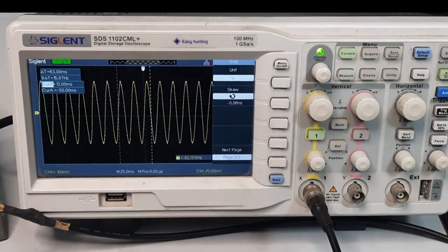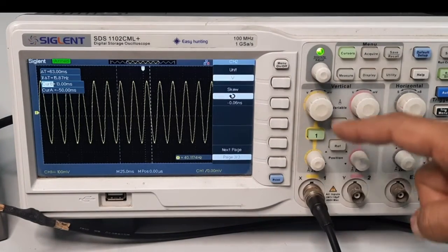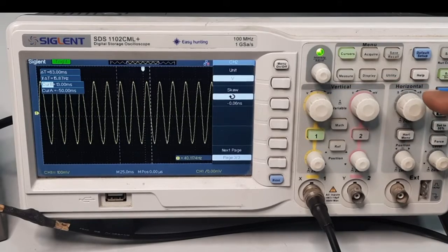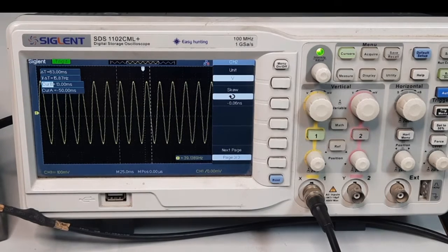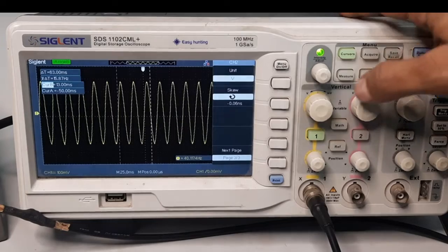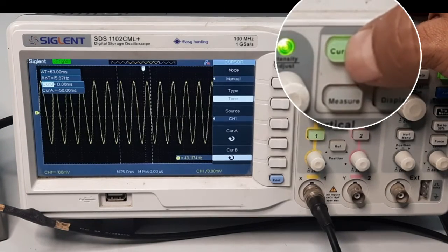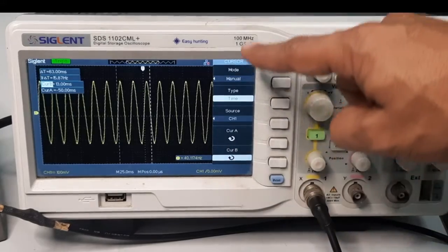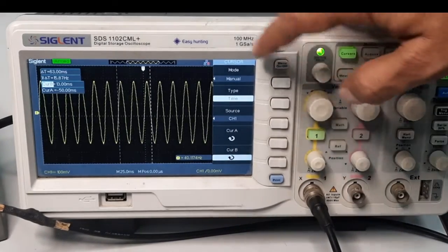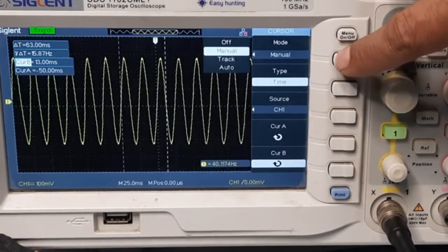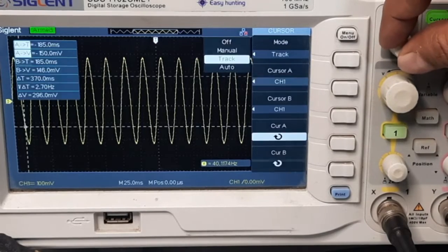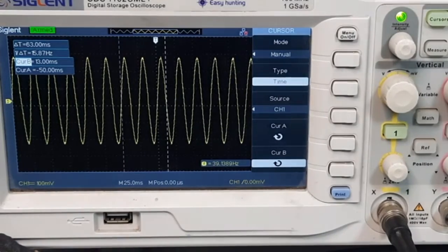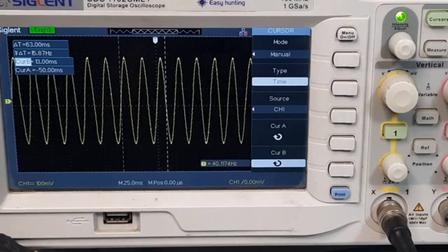So up to this point I have shown how to connect the cable, how to set the horizontal and vertical scale, and how to use the on/off channel buttons. Now I am going to demonstrate how you can measure the signal. For that, there is a cursor button. When I press the cursor button, a menu appears. The first option is the mode: you can see there are three options — manual, track, and auto. I can rotate the knob to select either of these, and I am fixing it to manual.